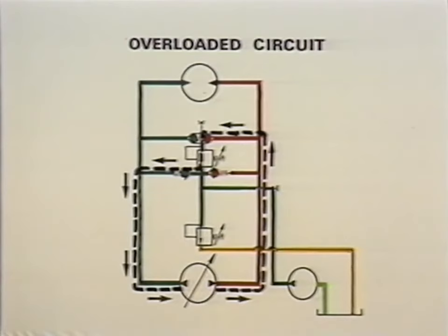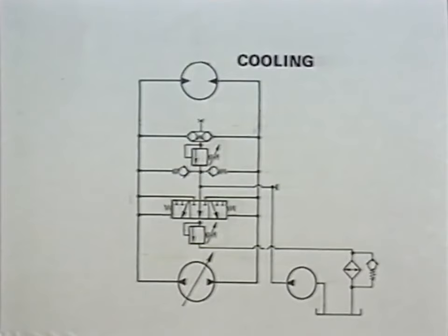When the entire flow of oil passes from the pump through the relief valve to the low pressure side, the hydraulic motor ceases operating. A double check valve sharing a common spring is connected to the pressure relief valve and allows usage of a common pressure relief valve for both the right and left-hand sides of the circuit.